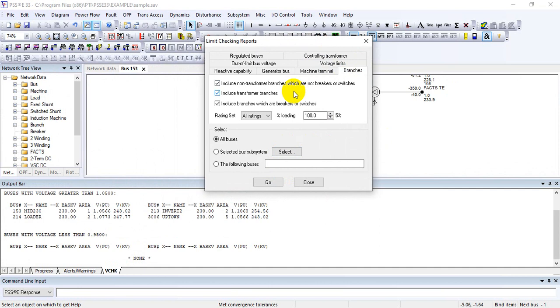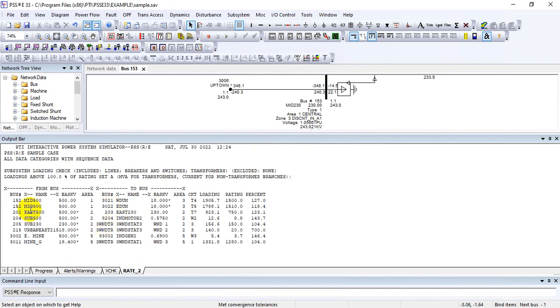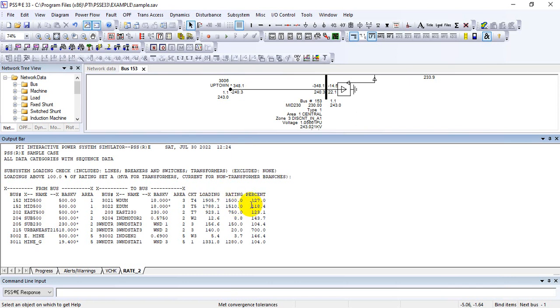Right after the voltage report, we can see the Branch Report — this covers thermal violations. To see any thermal violation, the branch loading threshold is set to 100 percent. The rating set should be set to Rate A. Select Rate A, then select all buses and click Go. A number of transmission branches violating the conditions will appear. For example, one branch going from a 500 kV bus to another — a two-winding transformer with a rating of 1500 MVA — shows a loading of 1905 MVA, which is 127 percent, meaning it is 27 percent overloaded.